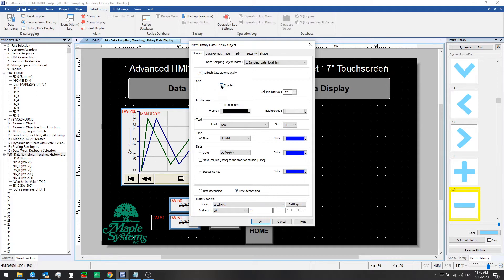Next we can set a grid and choose options for different colors for our profile and text. We can set the time and date to be shown, and then we can choose to either sort in descending or ascending order. With descending we're seeing the latest values that had been sampled every 10 seconds. Finally, with history control we can designate a register and enter in a value to control which day's data is shown.